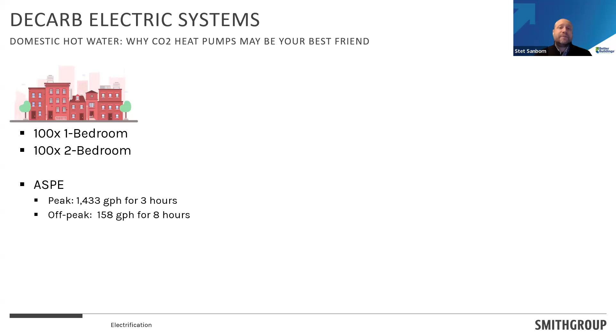If I were to achieve the domestic hot water flow rate with the bimodal distribution that we see in multifamily projects, and I'm going to do that with a traditional R134A heat pump, so this is a pretty traditional refrigerant, for that load profile, I would need 4 of those heat pumps plus almost 3,000 gallons of storage to be able to meet that load every day. But the number that I want to draw your attention to is in the middle of the slide at the very bottom, where you see 176 kVA. That's the connected load. That's what the panel board sees when you plug this equipment in.